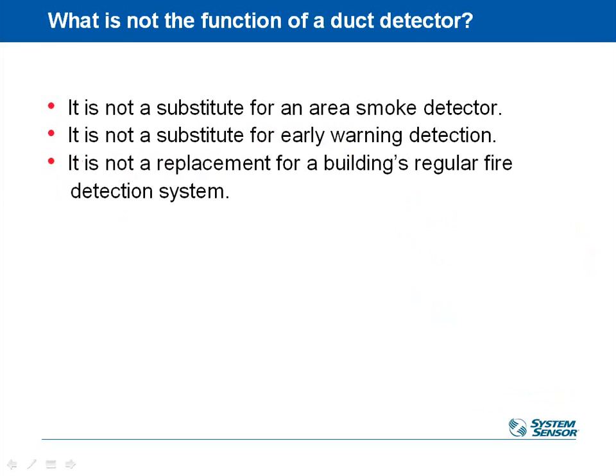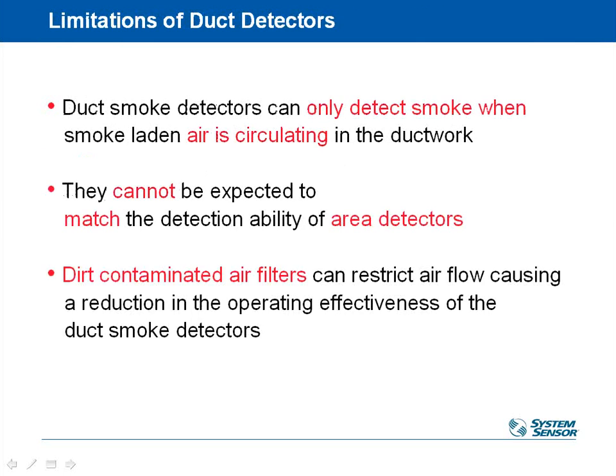All right, so what does a duct detector not do? It is not a substitute for area smoke detectors in the actual space. So some people like to think that, oh, instead of providing whatever 40 smoke detectors in this office building, if I put a duct smoke detector in, I don't have to put them in the office building. That is not true. The duct detector is supplemental to that system if that system is required. It's also not a replacement for any fire life safety systems like sprinkler systems or anything like that. Its job in life is just to sense the presence of smoke in the duct and stop spreading that smoke. That's all it does.